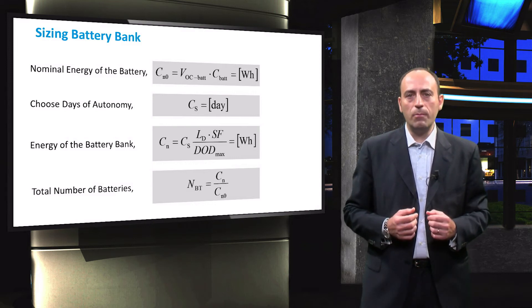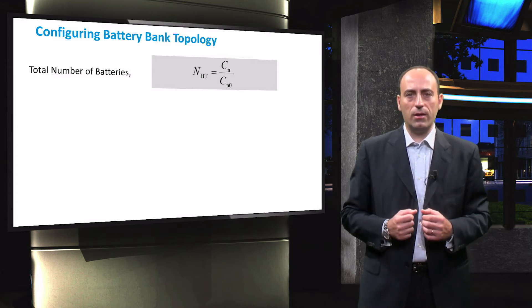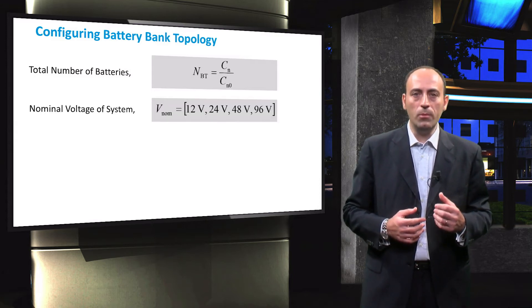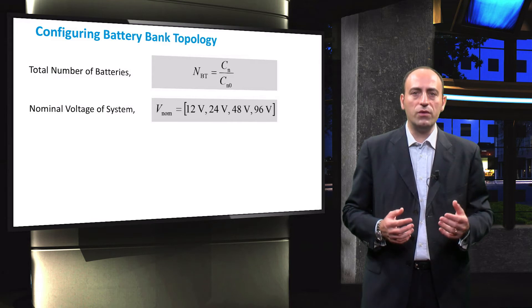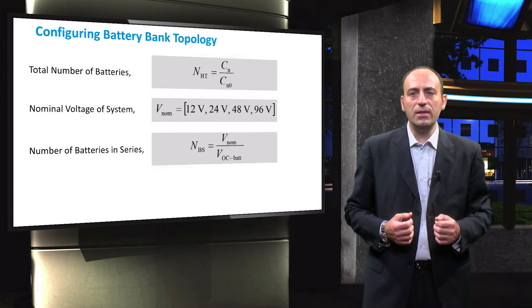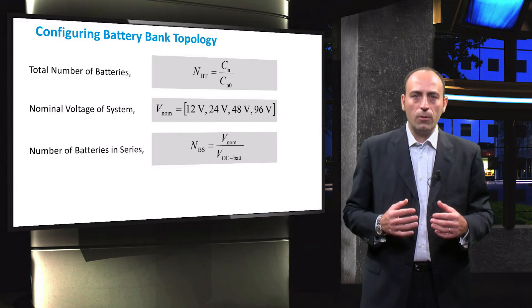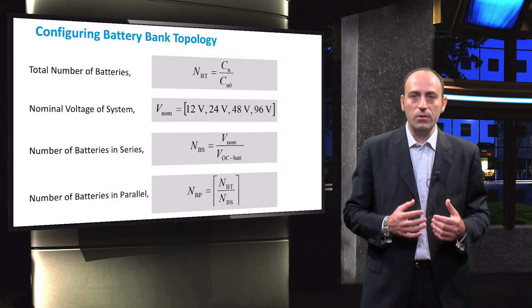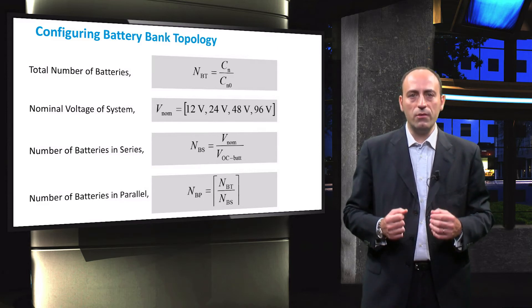Now the topology of the battery bank can be determined — that is, the number of batteries in series and in parallel. For the number of batteries in series, the nominal system voltage, VNOM, is chosen. Typical values for a standalone system are 12, 24, 48, or 96 volts. The number of batteries in series is calculated by dividing the nominal system voltage by the open circuit voltage of a single battery. The number of batteries connected in parallel is then determined by dividing the total number of required batteries by the number of batteries in series, with the resulting value rounded up to the nearest integer.